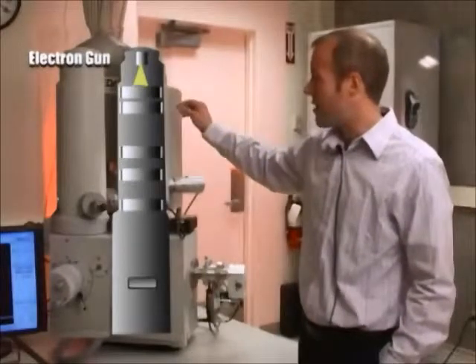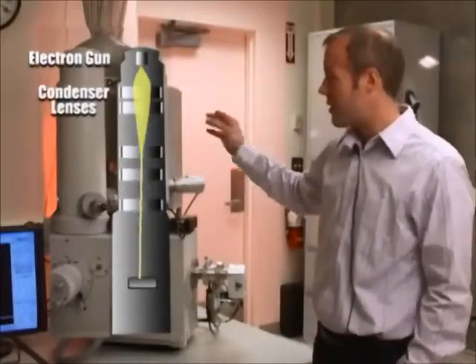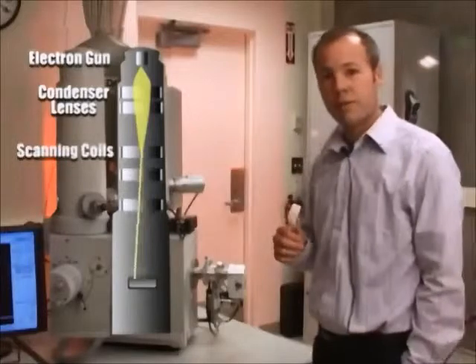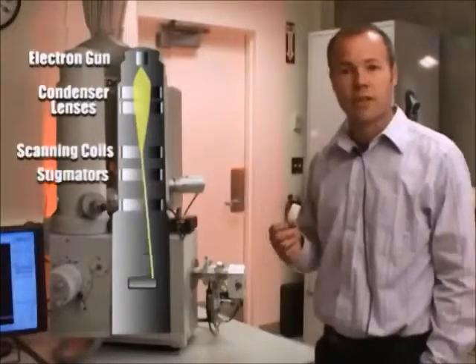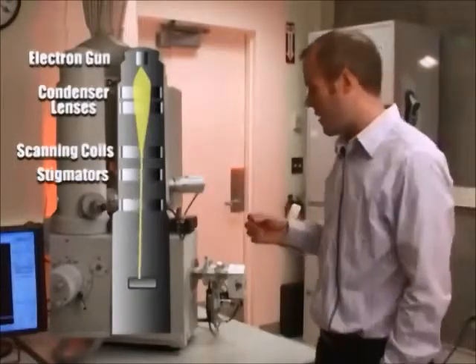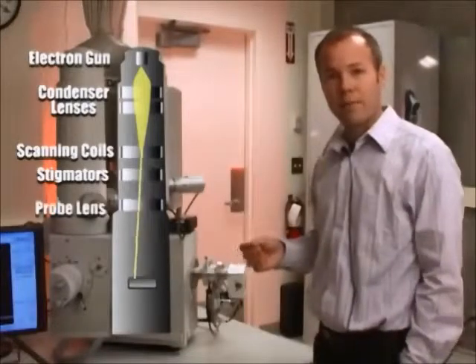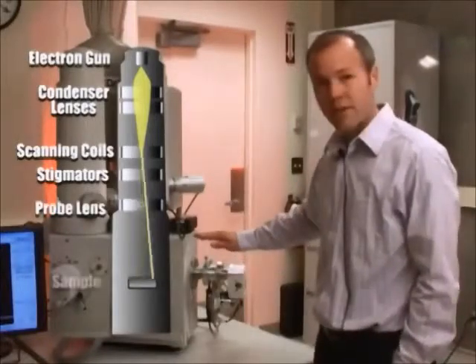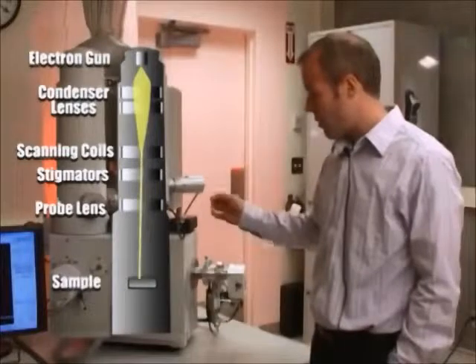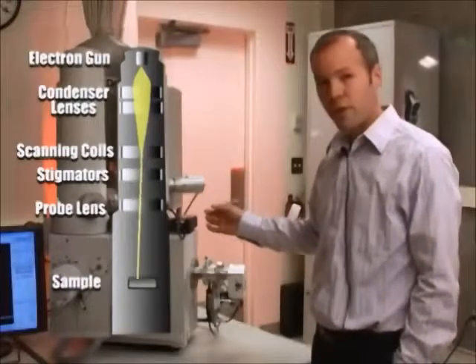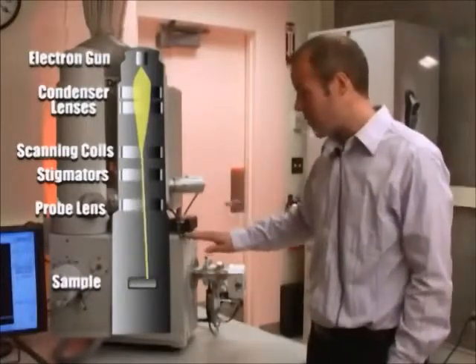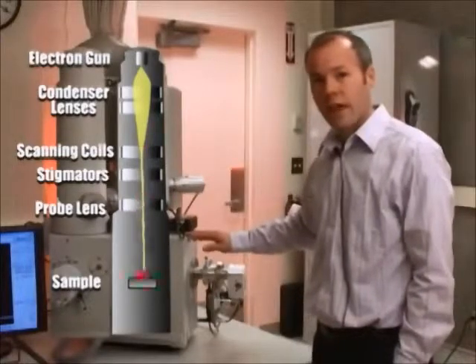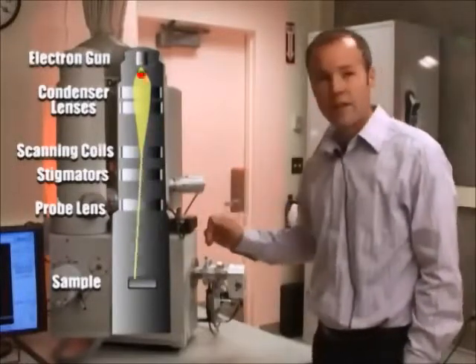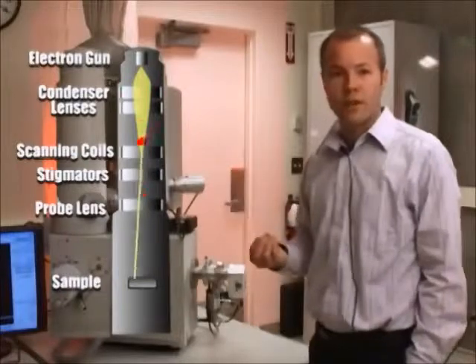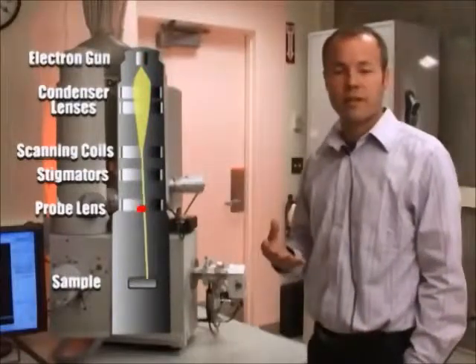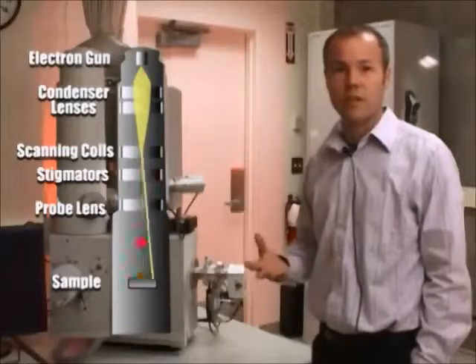Below the electron gun there are condenser lenses, scanning coils for moving the beam, stigmators for adjusting the roundness of the beam, and ultimately there's a probe lens at the bottom, down at about this level. When the probe, the electron beam, exits from the probe lens, it then enters the chamber, which is the square section here, and it impacts the sample, where the sample absorbs the energy of those electrons and then re-emits new signals that we use to image the sample.